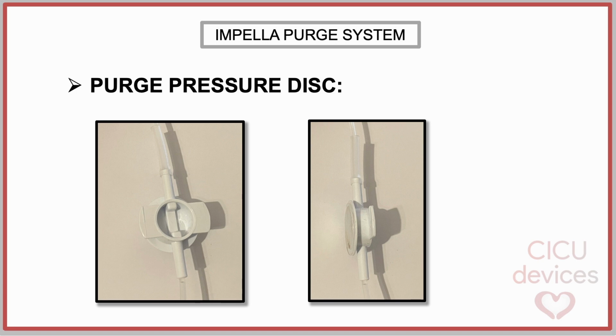Target purge pressures are typically maintained between 300 and 600 millimeters of mercury. Operating within this range ensures effective motor protection. Continuous monitoring of purge pressure via the purge pressure disc is therefore essential for safe, stable, and reliable Impella support.